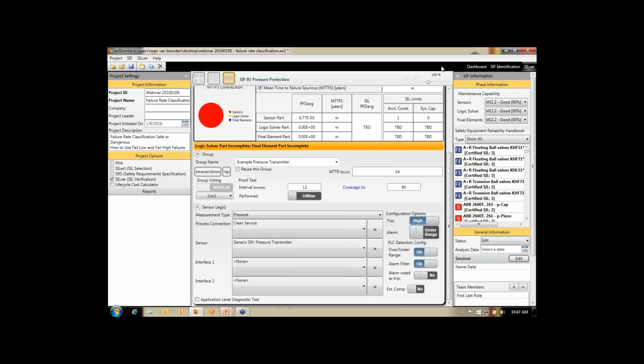the probability of failure on demand, because the time span that they're multiplied with is much smaller than the time span, for example, for the dangers undetected failures, which tends to be the proof test. But you should have noticed that the mean time to fail spurious went from something to infinity, because now we're filtering out all those votes for trips.